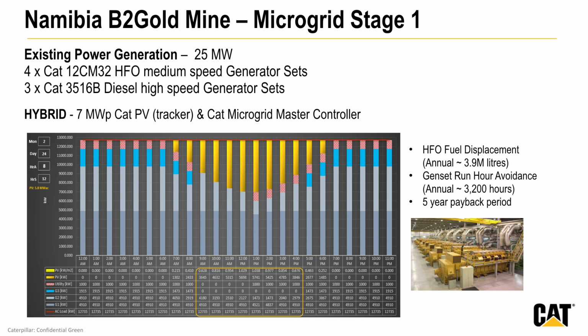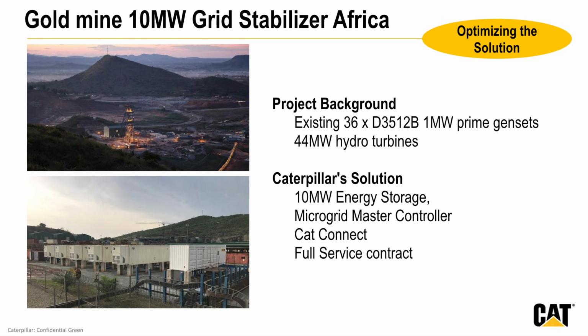This solar system addition allowed the shutting off of one of the large units during the daylight hours and resulted in 3.9 million litres of fuel displacement and genset run hour avoidance of 3,200 hours per year, which resulted in a 5-year payback period. Now, moving on to the next project, this is another gold mine in Africa, which had an existing power system to begin with. It had 44 megawatts of hydro turbines and 36 1 megawatt Caterpillar 3512 gensets. Of course, the hydro is intermittent depending on rainfall in the region.